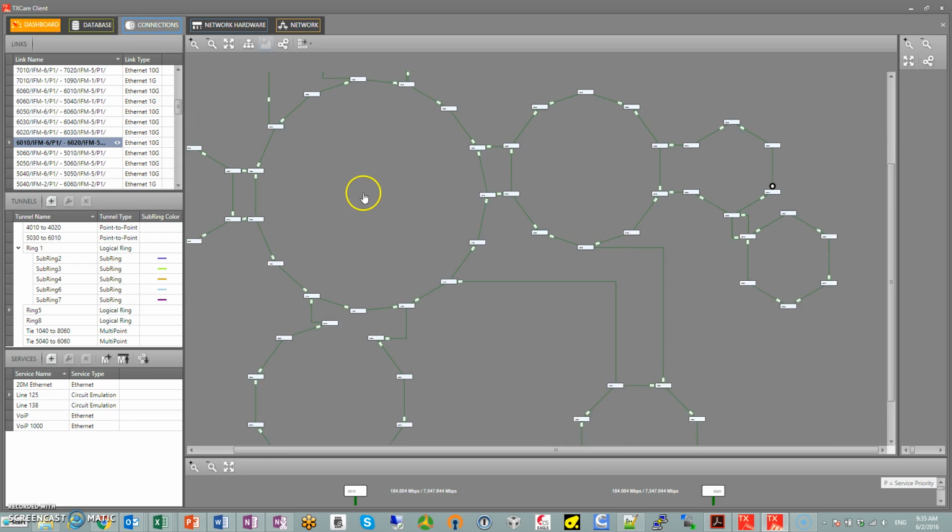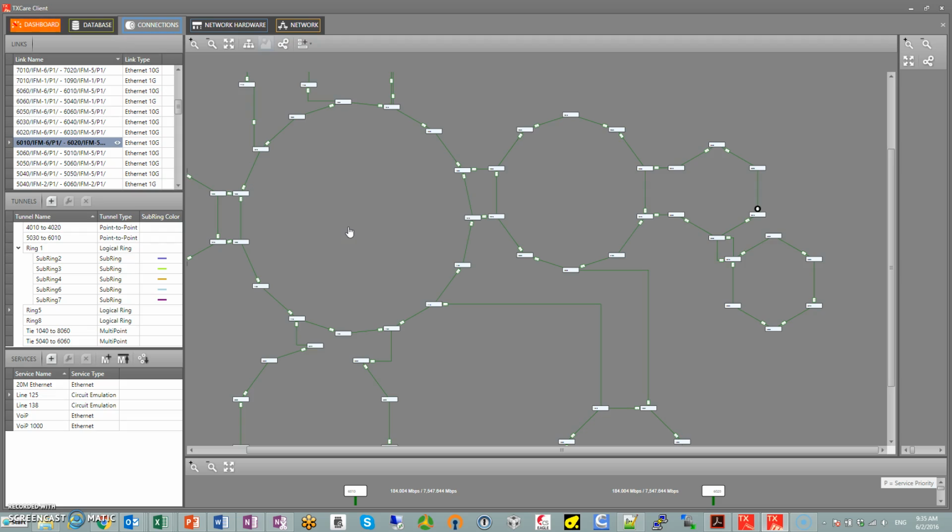All right, so let's create this service. Before we do that, we need to make sure that we have the tunnels to reach out to that, and we do. Keep in mind that what we're going to use is RS232, not over circuit emulation, because that would be point-to-point, typically mirrored bits. We're going to use a packetized or serialized RS232 byte that gets mapped directly into an Ethernet frame, and that eventually will be transported over Ethernet, so we could do this over a ring topology here.